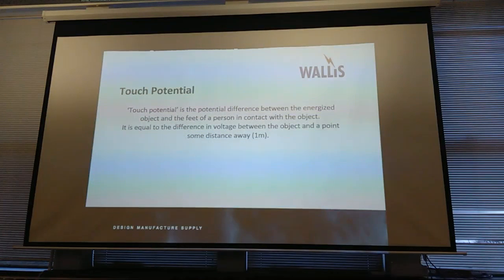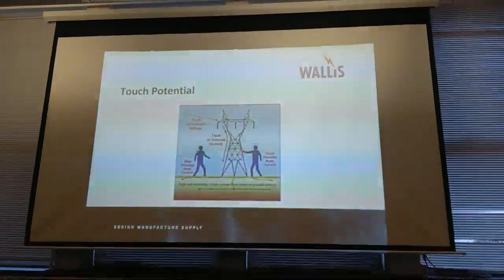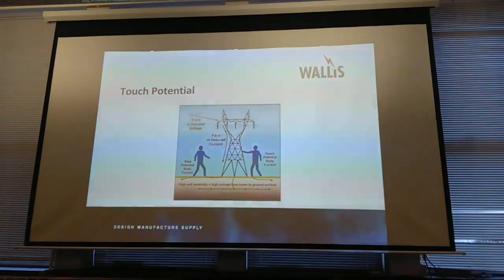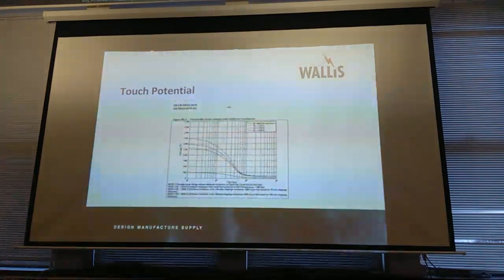Again, touch potentials, sorry, I'm flip-flopping around a little bit with this. Touch potential is the potential difference between the energized object, so it's a substation, and the general mass of earth that you're standing on a metre away. So it's that potential difference through the body into the ground, and it's that loop. Very much as that little chap standing there. That's just an extract from 50522, showing you the permissible limit. You've got the time along the bottom in milliseconds and the permissible touch voltage up the left-hand side.